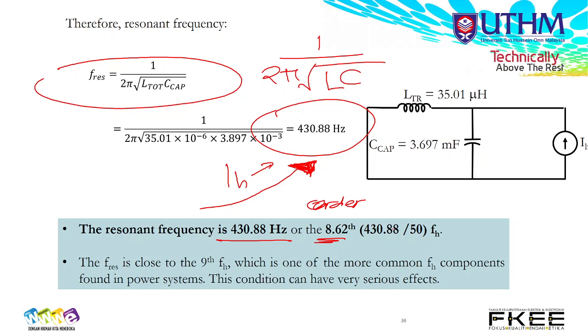So how do we calculate? 430.88 divided by fundamental frequency, divided by 50, so we get 8.62, which is close to the 9th harmonic order of the frequency. The resonance frequency is actually close to the 9th frequency, which is also one of the more common frequency components found in power system problems.